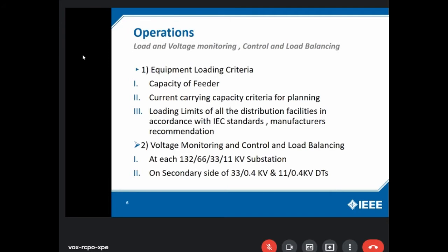Number three is loading limits of all the distribution facility in accordance with IEC standards and manufacturer recommendations. Standby rating is not to be considered while designing and planning of the network and the limits of the equipment. And now the voltage monitoring and the control and the load balancing, of course.